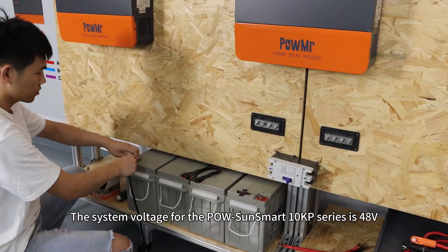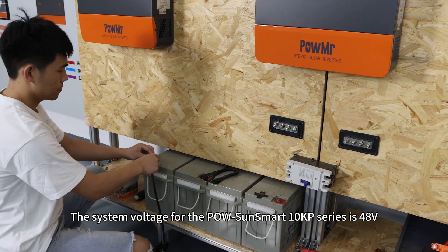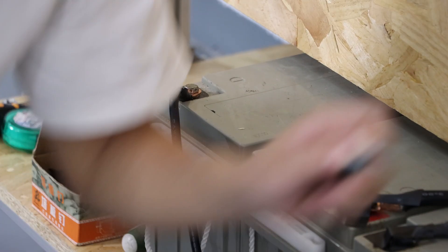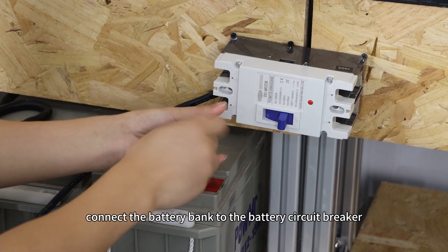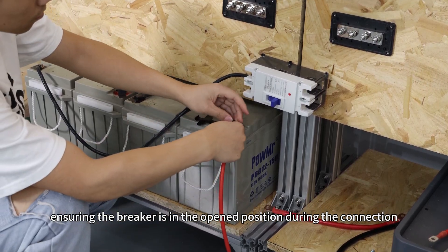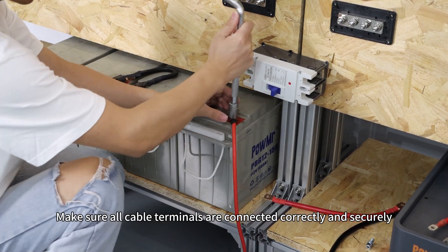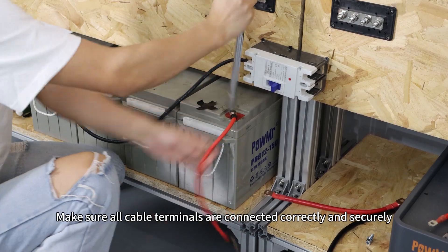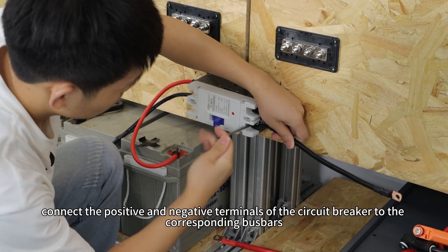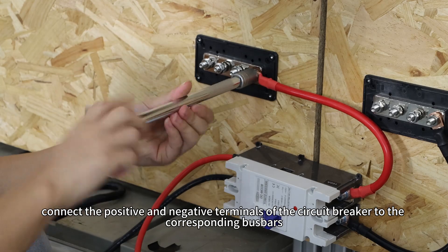The system voltage for the POW-SunSmart 10KP series is 48V. All inverters should be connected to the same 48V battery bank. First, connect the battery bank to the battery circuit breaker, ensuring the breaker is in the open position during the connection. Make sure all cable terminals are connected correctly and securely. Then connect the positive and negative terminals of the circuit breaker to the corresponding bus bars.